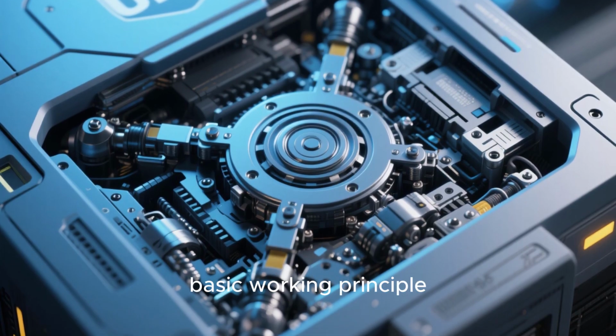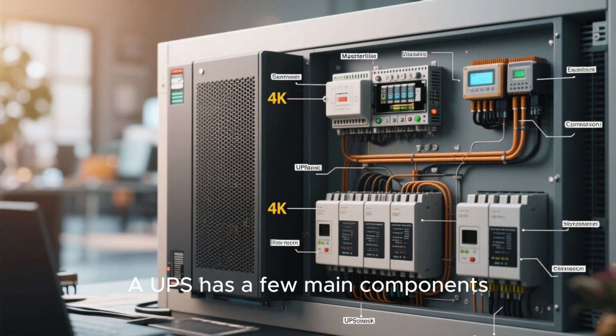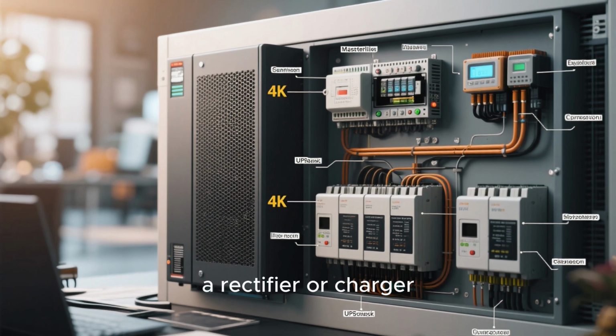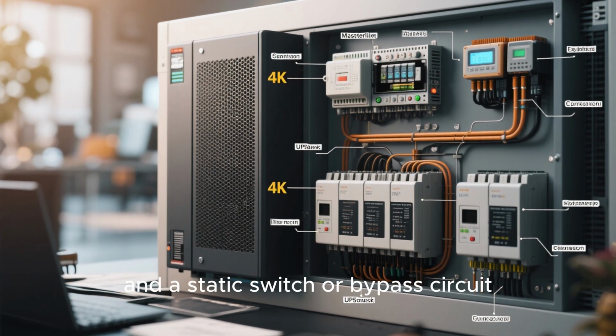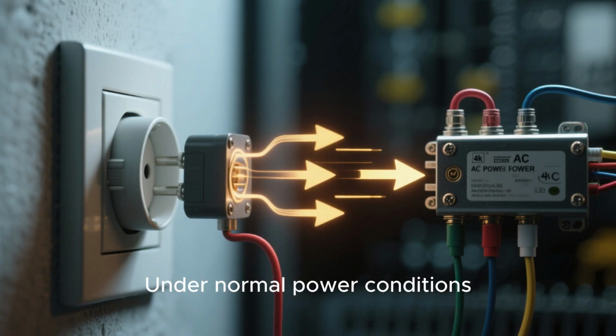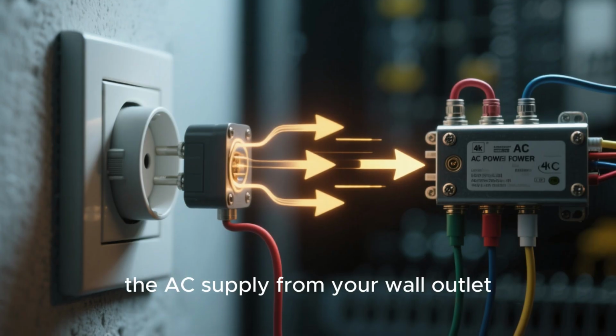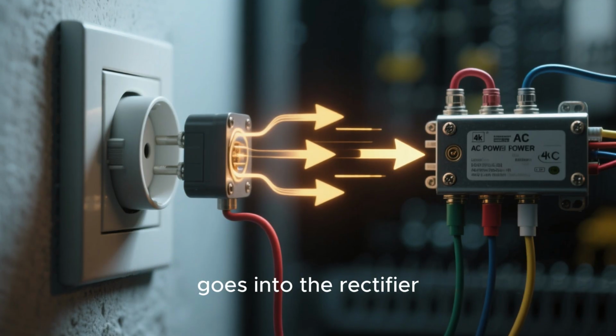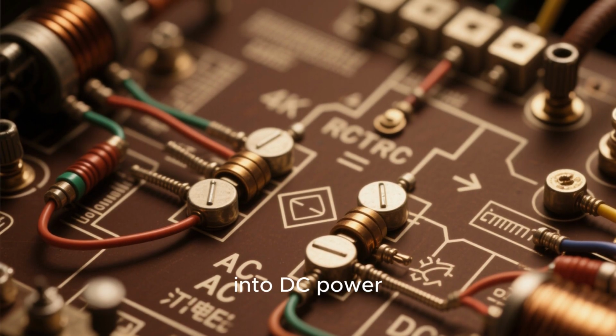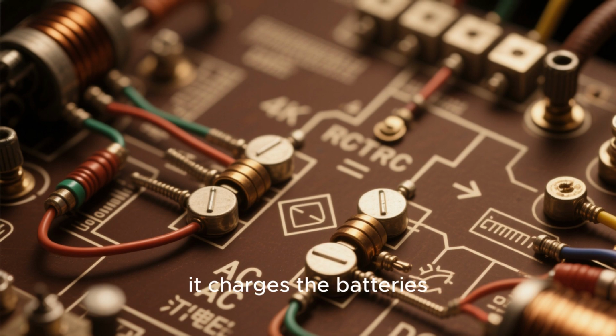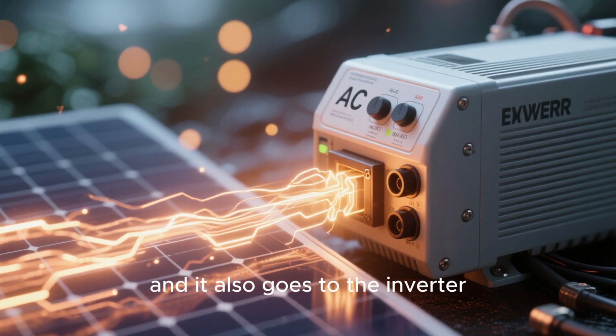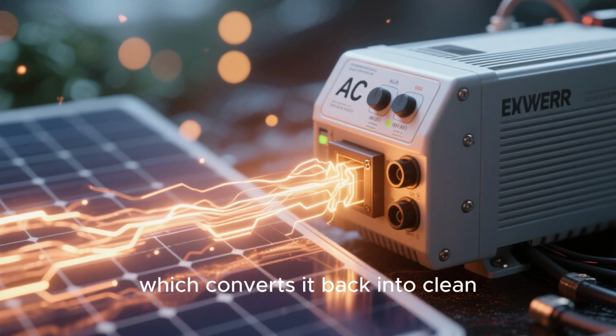Let's look at the basic working principle. A UPS has a few main components: a rectifier or charger, a battery bank, an inverter, and a static switch or bypass circuit. Under normal power conditions, the AC supply from your wall outlet goes into the rectifier. The rectifier converts this AC power into DC power. This DC power does two things. It charges the batteries, keeping them full, and it also goes to the inverter, which converts it back into clean, stable AC power to supply your equipment.